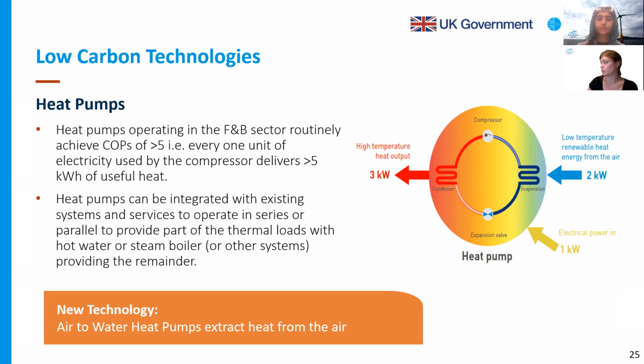Heat pump efficiencies are typically mentioned in the form of coefficient of performance, just like the chillers. So the ratio of heat delivered by the heat pump is in the numerator, divided by the amount of electricity required to drive the heat pump. Heat pumps can be integrated with existing systems and services to operate in series or in parallel to totally replace or provide part of the thermal load.